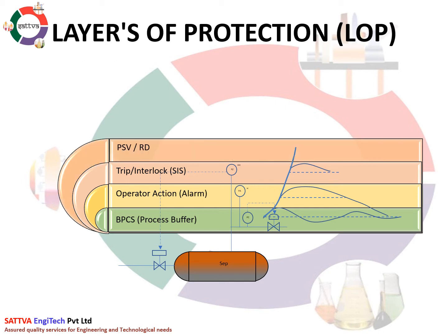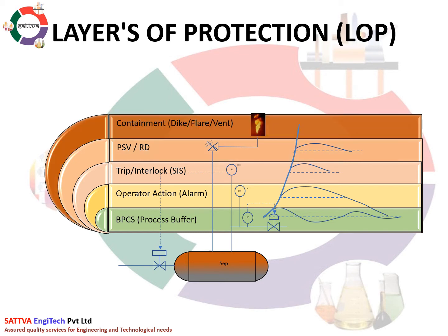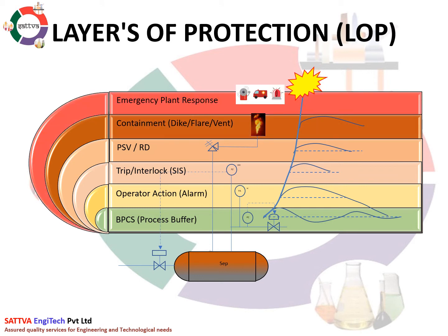If this layer fails, then the next layer of protection is a mechanical device such as a pressure relief valve or rupture disk, opening and releasing the content to a safe location. This layer protects from major damage and uncontrolled loss of containment, keeping the overall system safe. The next layer is containment to a safe location such as a dike, vent or flare, wherein containment is released safely with consideration of flammability, toxicity and potential hazard to personnel and the surrounding community. If all the above layers fail, audio-visual alarms notify all personnel with a medical support team to take action.